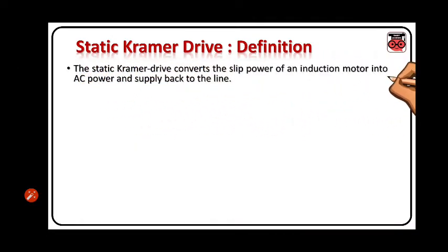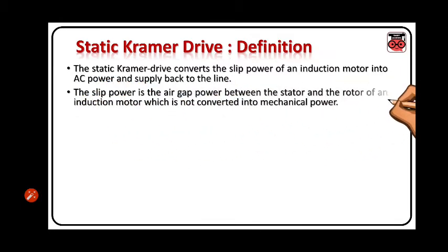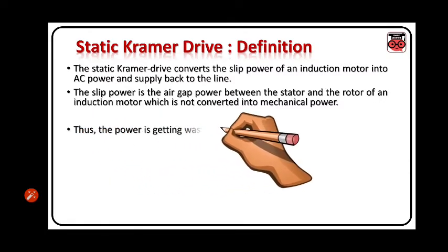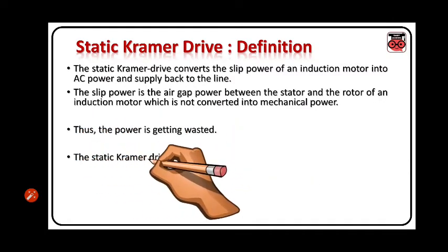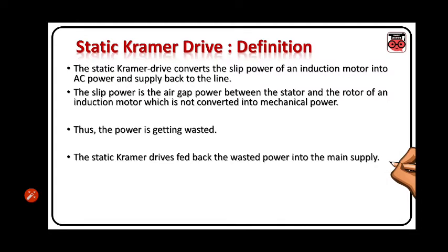The static Kramer drive converts the slip power of an induction motor into AC power and supplies it back to the line. The slip power is the air gap power between the stator and the rotor of an induction motor which is not converted into mechanical power. As the power is getting wasted, the static Kramer drive feeds the wasted power back into the main supply.